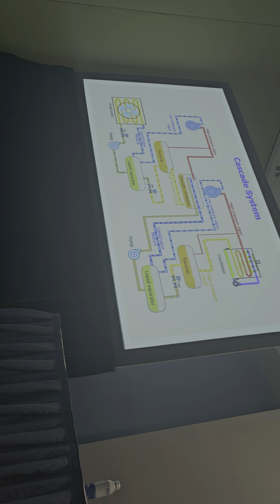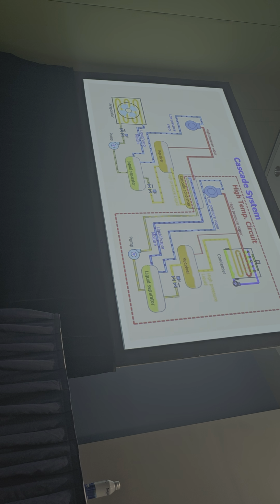These refrigeration systems usually consist of one or more separate refrigeration circuits, often using different refrigerants to provide the cooling effect. In this system we have two compressors, each circulating refrigerant around separate circuits: a high temperature circuit and a low temperature circuit. Connecting the two circuits is a heat exchanger known as a cascade condenser, which acts as a condenser. That's a simple cascade system.